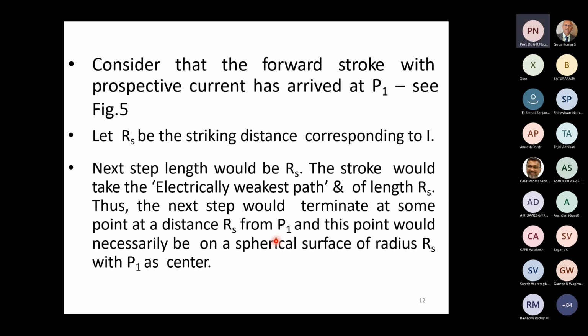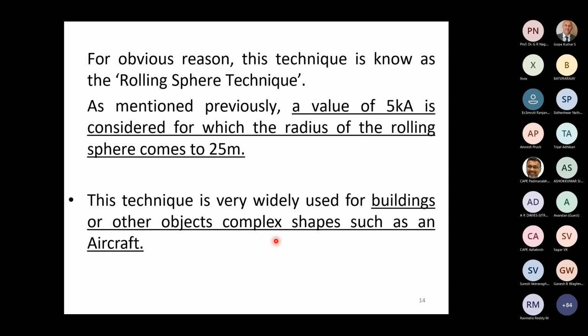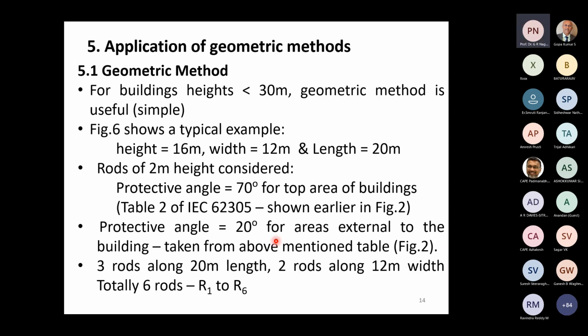Now, supposing I have a tall building, I want to protect it down to 5 kiloamperes. For the 5 kiloampere stroke, which I would like to consider very safe for the building, the striking distance is 25 meters. Okay, before I go further, I would like to mention one thing, which I mentioned earlier also. If the building height is less than approximately 30 meters, or about 100 feet, the geometric method is quite directly applicable. You don't have to worry about the rolling sphere technique.